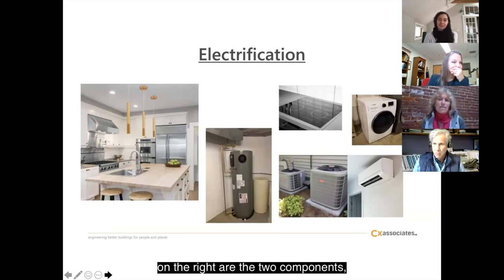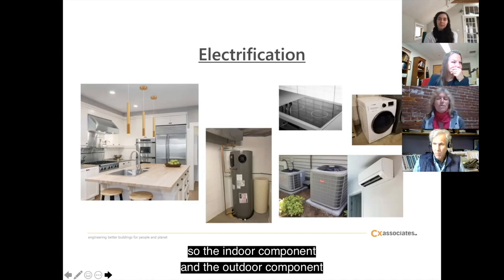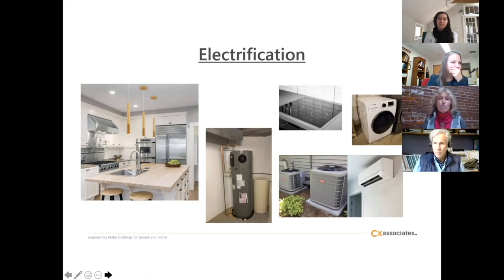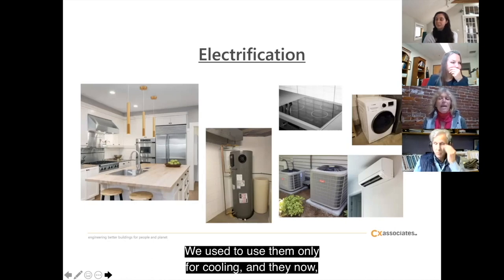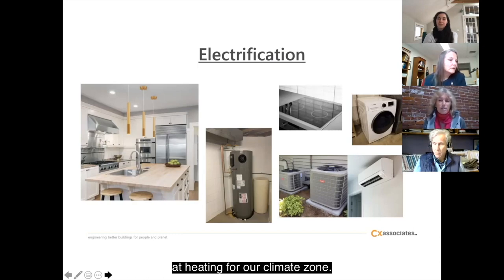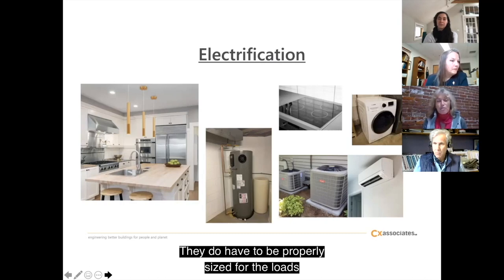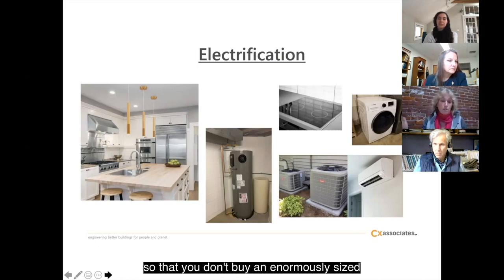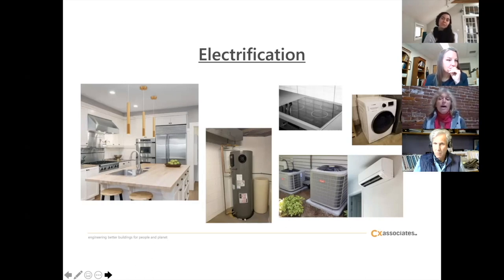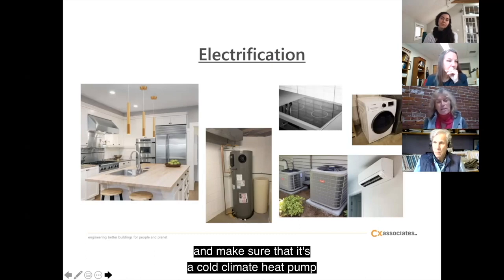And then the bottom two pictures on the right are the two components, the indoor component and the outdoor component, of an air source heat pump. I'm sure everybody's been introduced to heat pumps. We used to use them only for cooling, and now, especially cold climate heat pumps, are very effective at heating for our climate zone. They do have to be properly sized for the loads in your building. So again, weatherization is really important to do first so that you don't buy an enormously oversized piece of equipment. And make sure that it's a cold climate heat pump, because they keep getting lower, but they can work down to about negative 15 degrees and still be very effective.